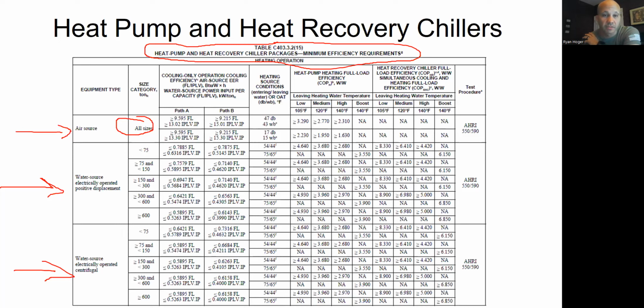So I get to the right table, I find the kind of machine that I have, and then I find my tonnage. We'll just stick up here on the air source for right now to make it clean. You have, and this is already getting more complicated than it needs to be, right? But you have path A and you have path B. And the reason you have that is because regular chiller efficiency also has path A and path B. What that means from a code perspective is that you can follow either path A or path B, one or the other. You do not have to meet both.